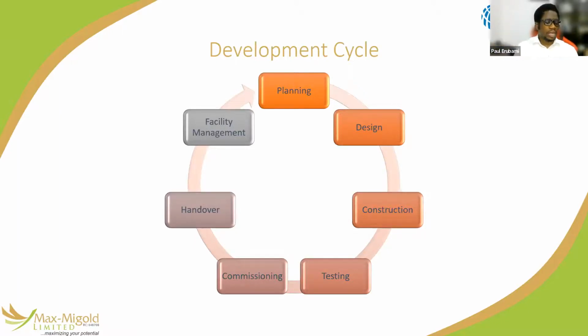So you can have an AC working, tested okay, and all the operating parameters are okay, but the AC does not cool based on the activity performed in the room. When we sit down and take a class in a room, the AC requirement is much reduced. But if that room is designated for a party, a nightclub, a church service where you're dancing and doing all kinds of stuff, you definitely require additional air conditioning. So it's not enough to say the air conditioning works.